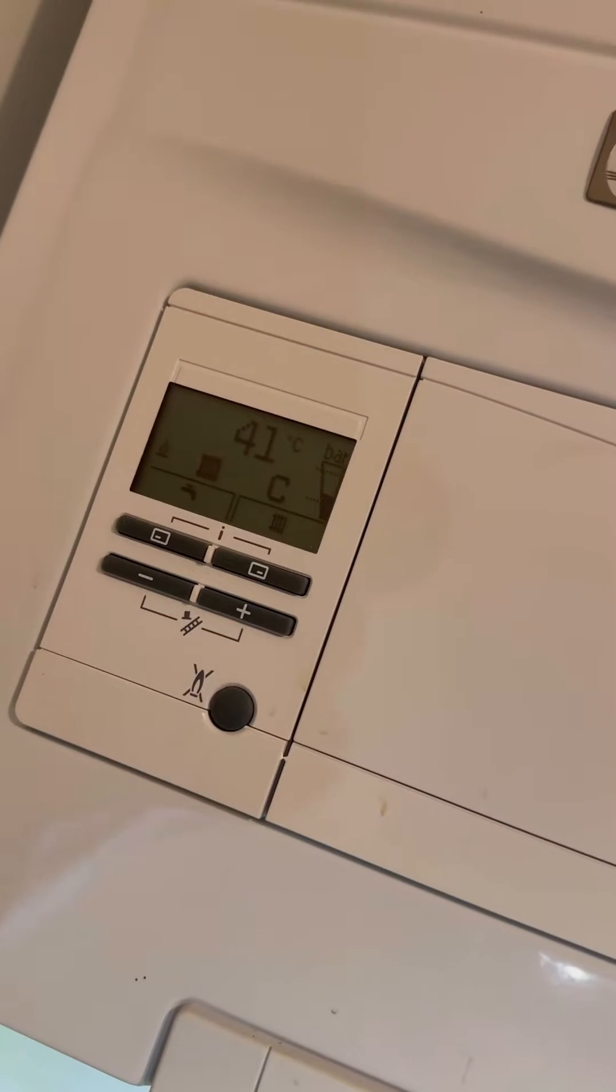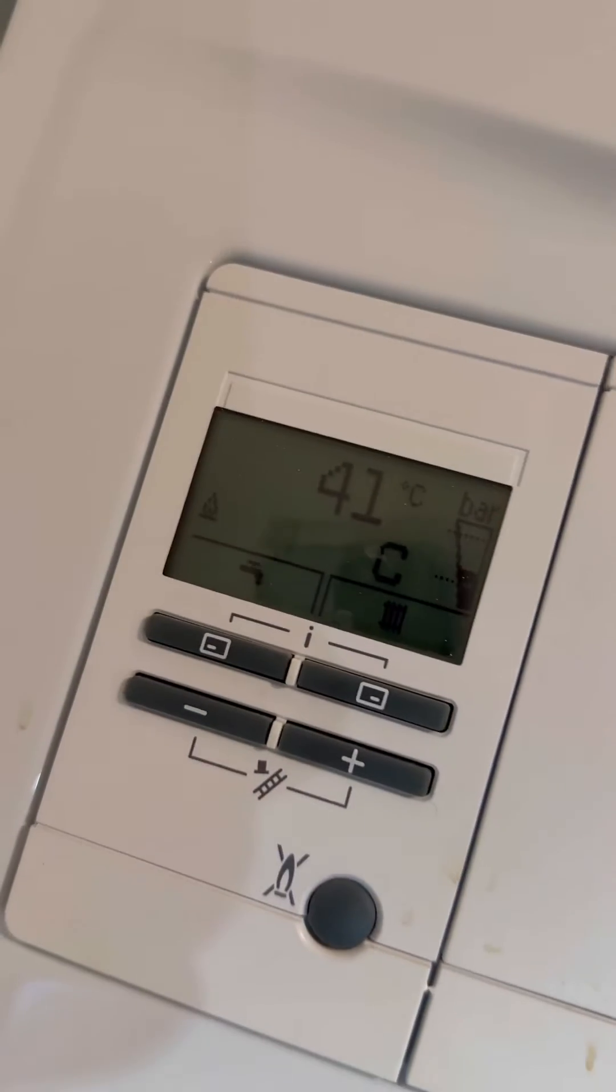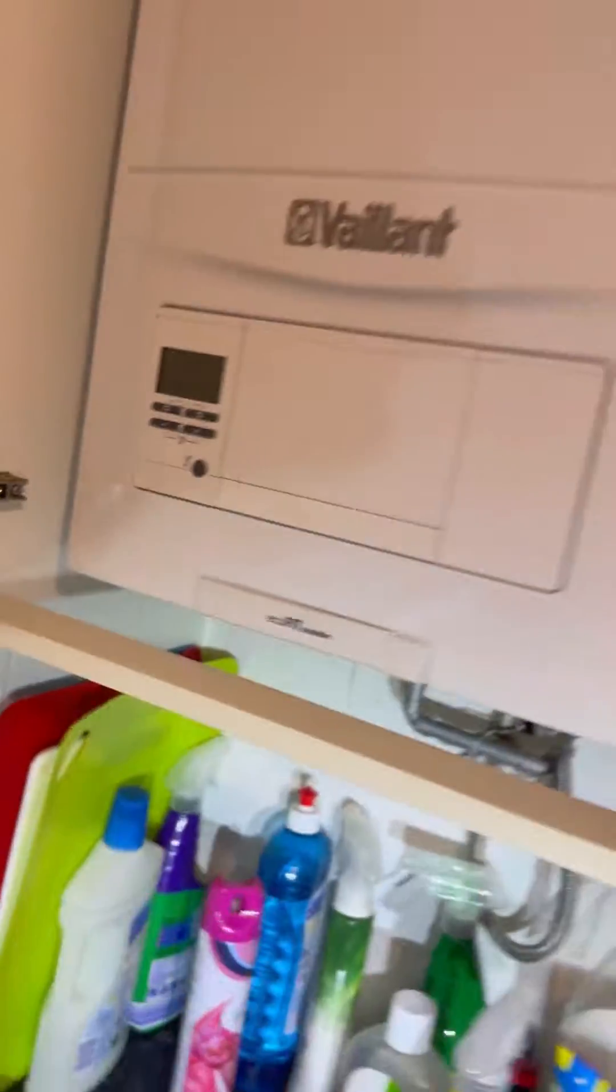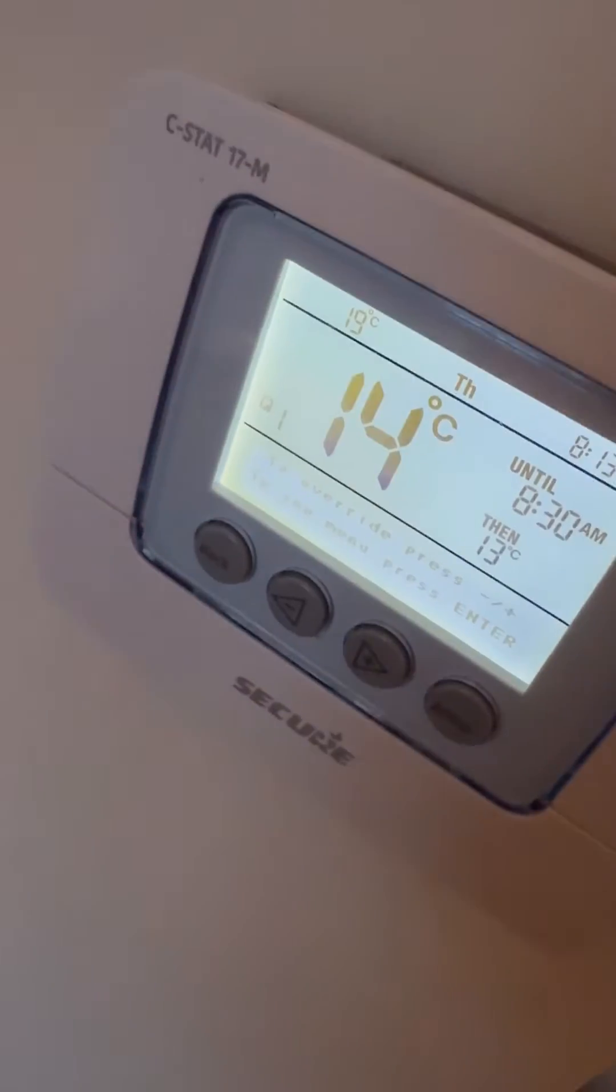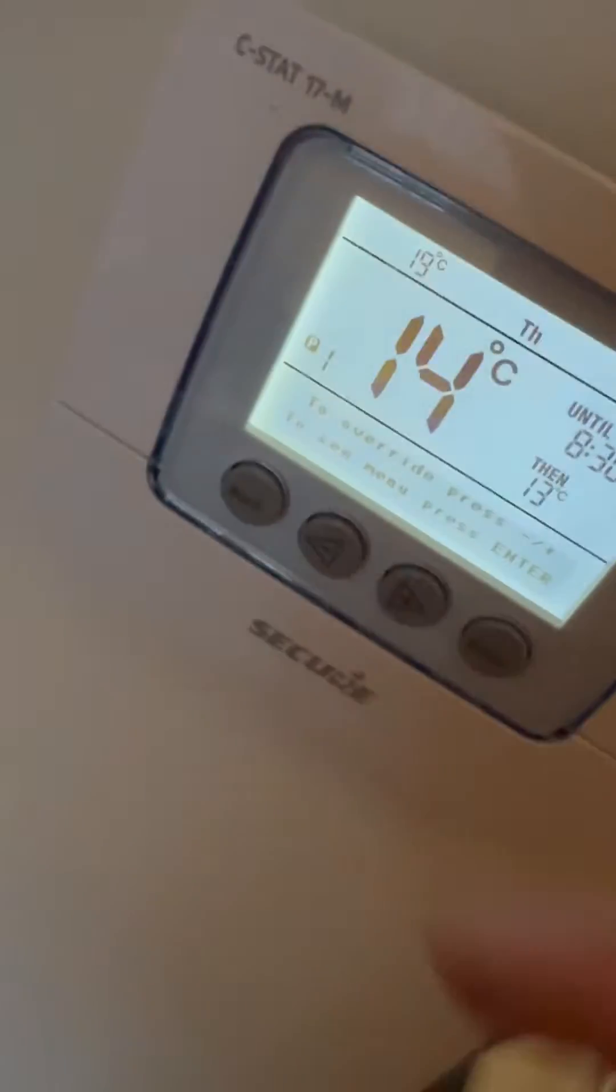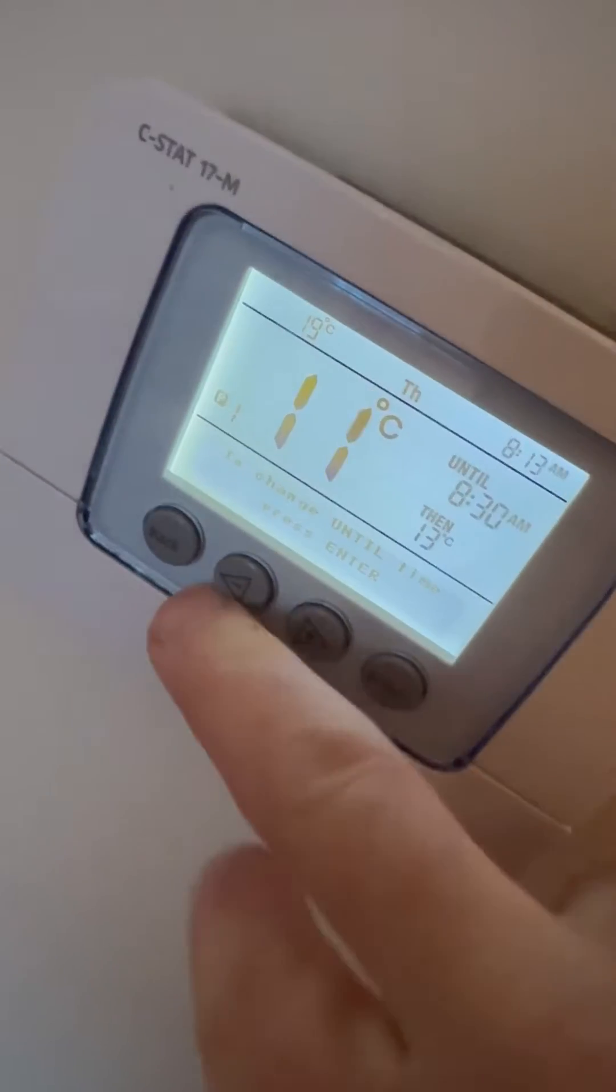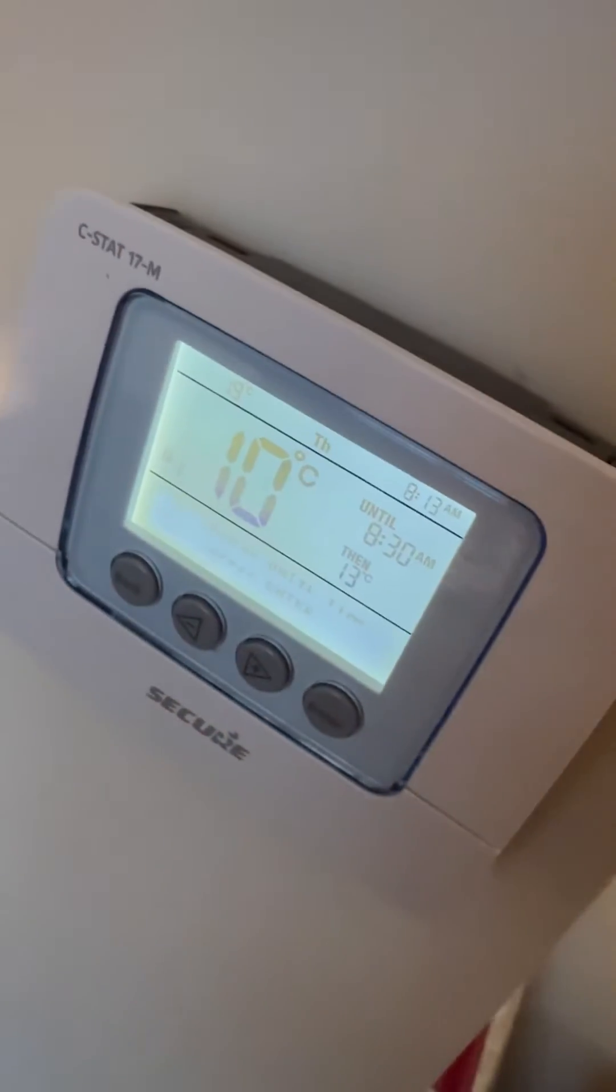Turned up to this Vaillant EcoFit Sustain combi boiler. They were saying the heating's on all the time. It's a new build so it's zoned upstairs and downstairs. Checked the first programmable stat - that's not calling. Second not calling either, but the boiler was. So let's head up to the airing cupboard.